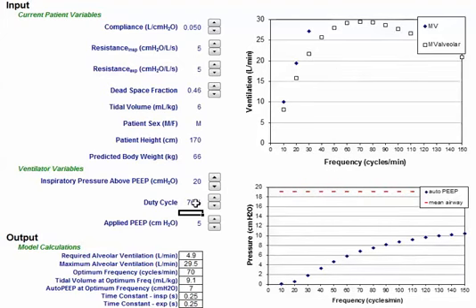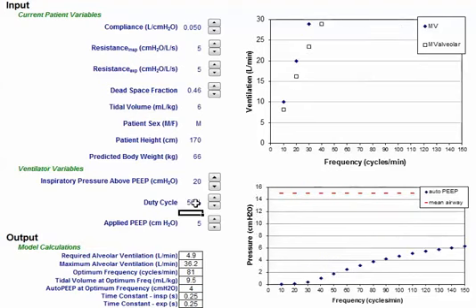So I can't lengthen my inspiratory time anymore and gain anything else. Let's change this back to my 1 to 1 ratio, my optimal duty cycle setting when resistance values are the same. And what happens if my inspiratory resistance is more than my expiratory?